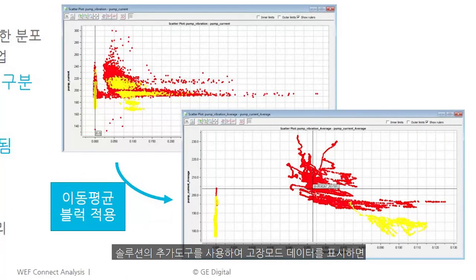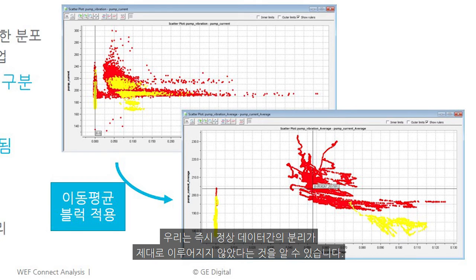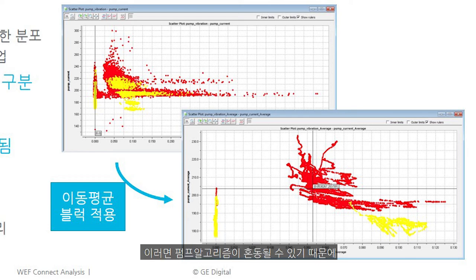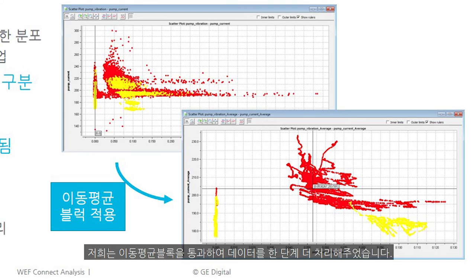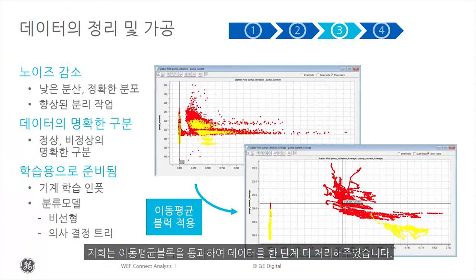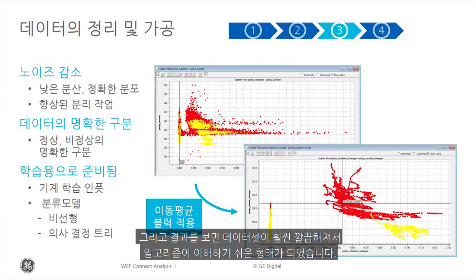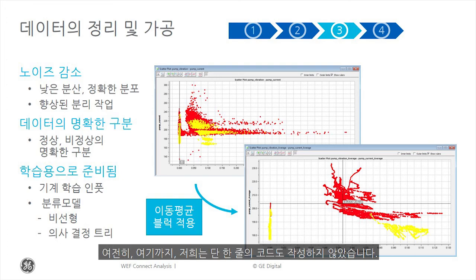Using additional tools in the solution to mark the failure mode data, we immediately realized that we did not have that good separation needed between the normal data and what we had marked as the failure data. This would confuse the pump failure algorithm. So we took a step to quickly process the data by passing it through a moving average block, and the result was a much cleaner data set that the algorithm would understand much better. Still, to this point, we have not written a single line of code.